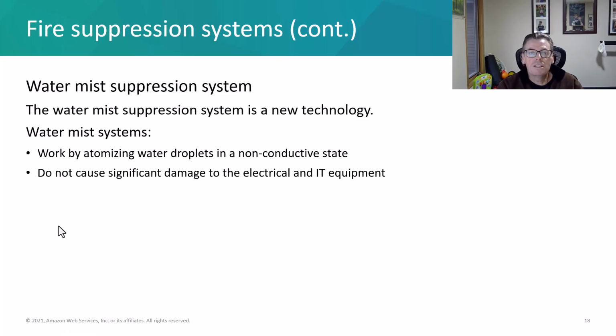All right, water mist suppression. It's a newer technology, and it works by atomizing the water droplets into a non-conductive mist. It doesn't cause significant damage to the IT equipment because it's a misting and not a flooding event. I'm not super familiar with these water mist suppression systems, and I'm only basing my understanding on what I've read about them and what I've seen in videos as well.